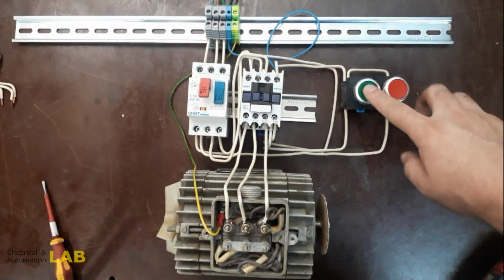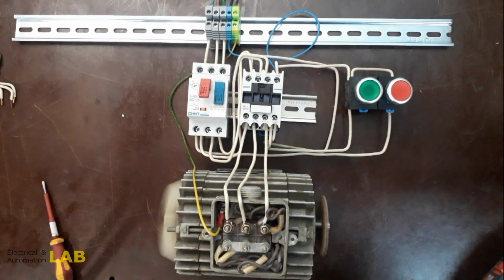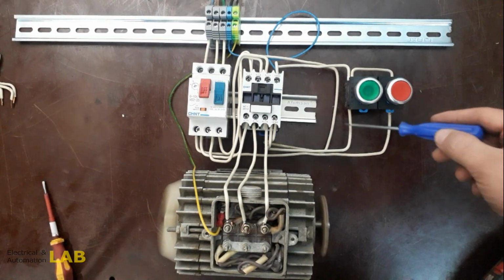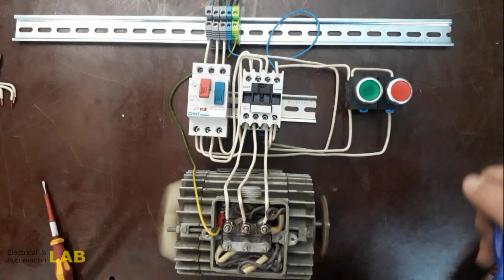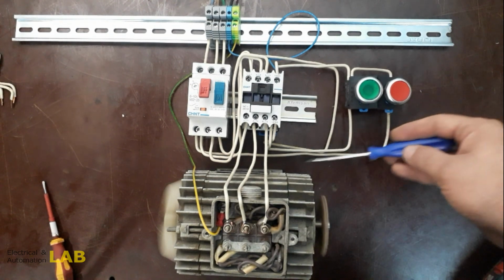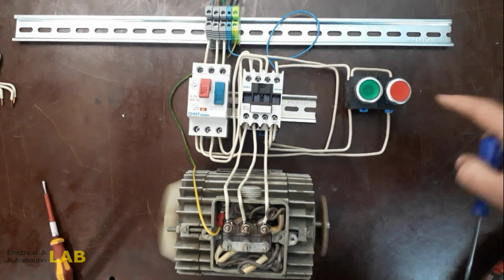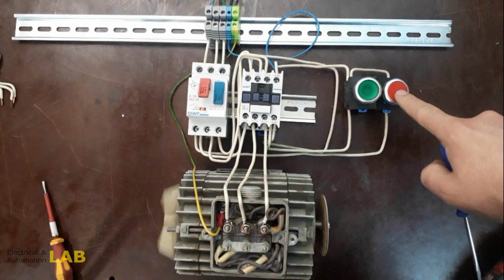Let's try. As you can see, the contactor has closed, 3-phase voltage is applied to the motor through the circuit breaker and then through the contactor. We press the stop button. Since the coil power passes through the stop button, the circuit is broken and the contactor opens.